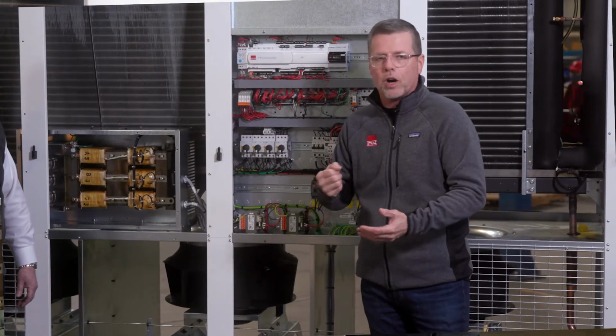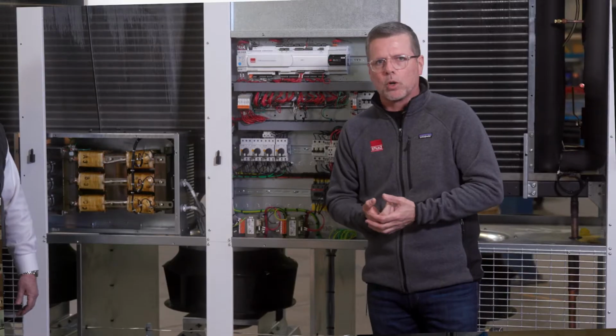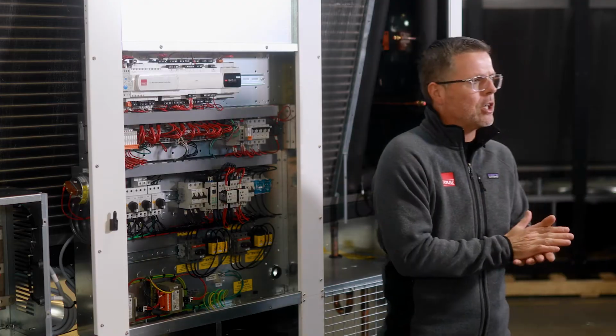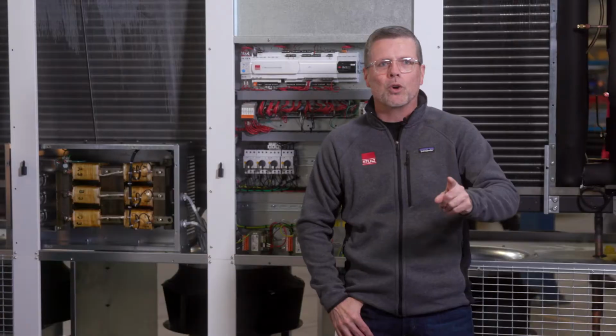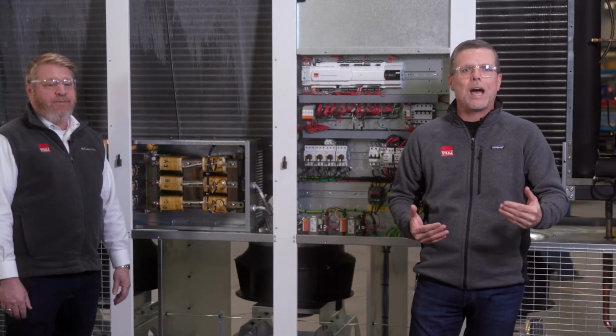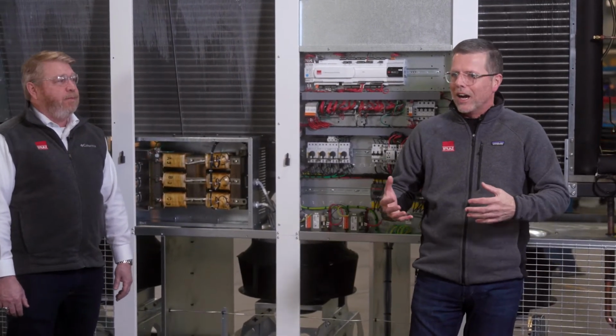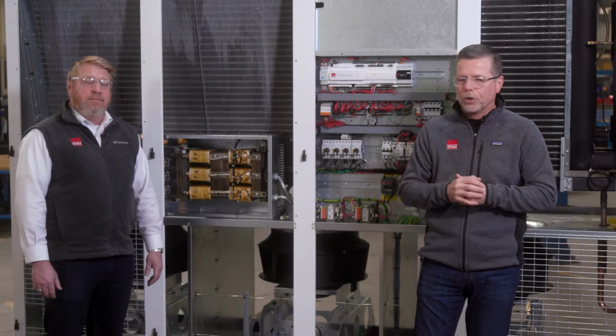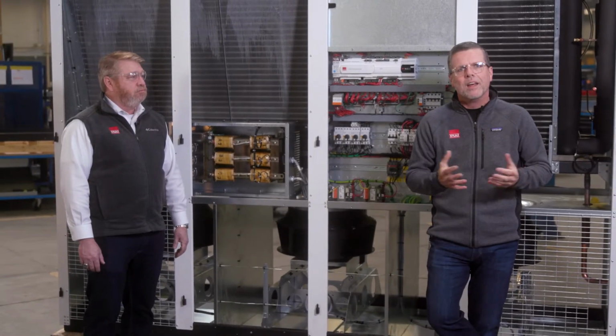The controller itself, we've talked about the BMS protocols available. The network management card, the BMS card can support HTTP, SNMP, Modbus RTU, Modbus IP, BACnet TCP, BACnet IP, probably missing a few, but the one we will not say, but we say on every video is LonWorks. We do not support LonWorks, but I assure you we will work with you if you happen to have a LonWorks opportunity there. There's integrators, there's third-party devices where it's not an issue.